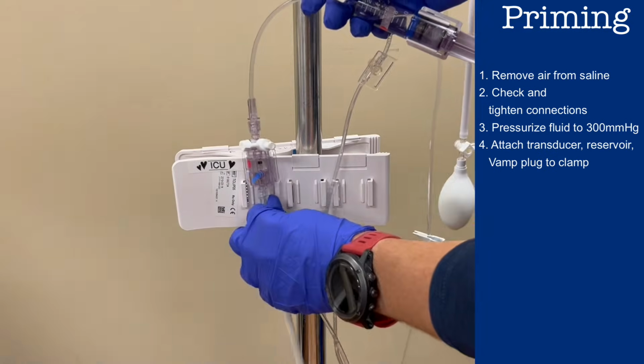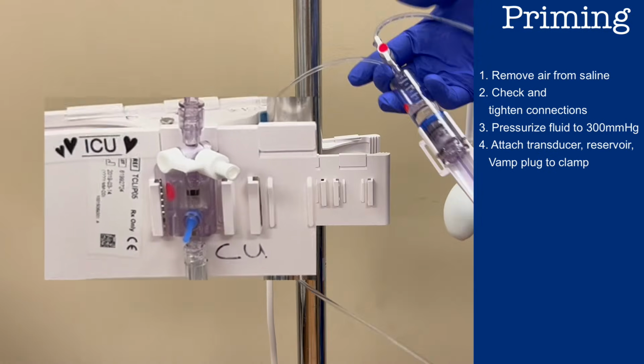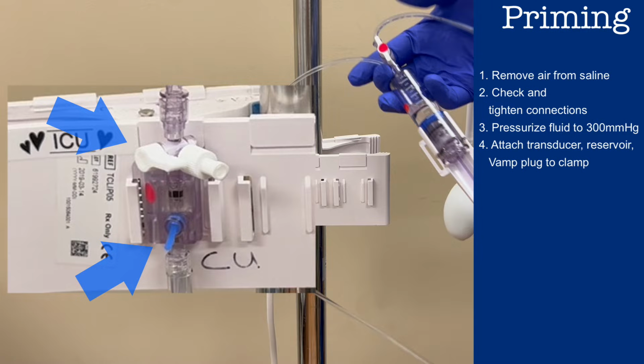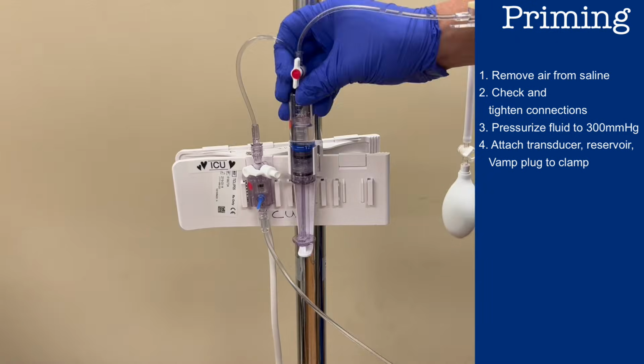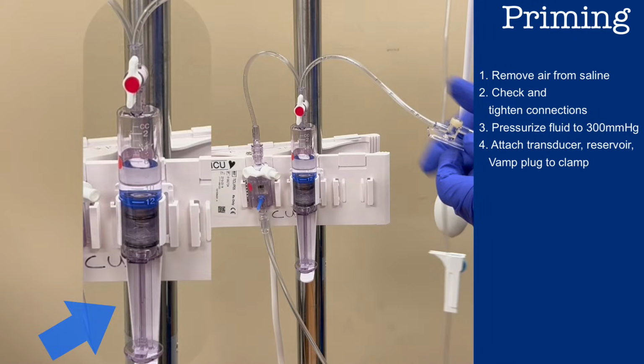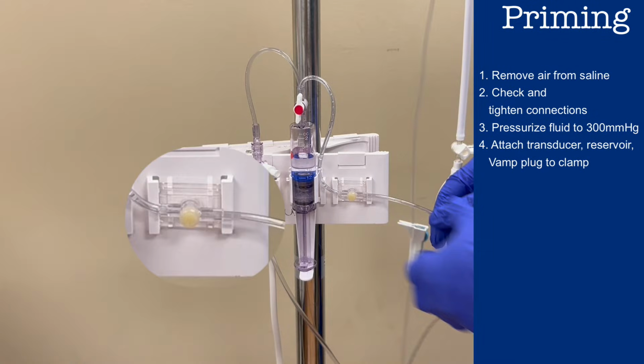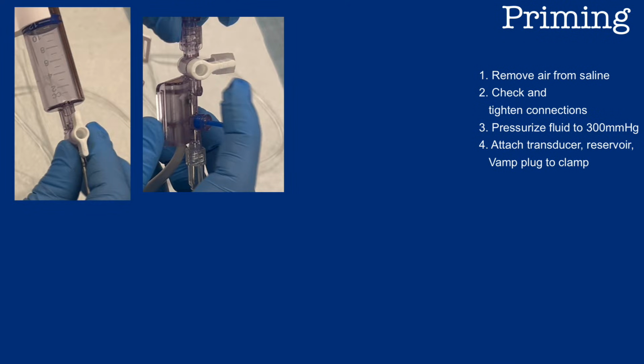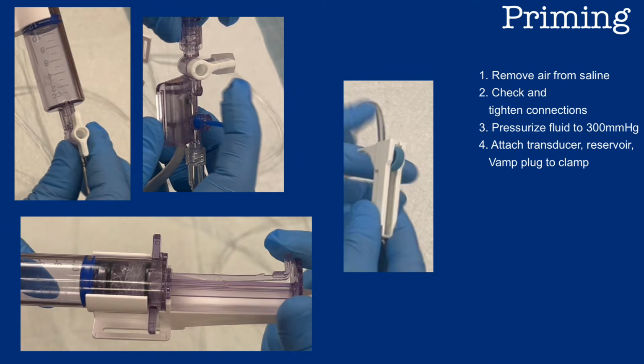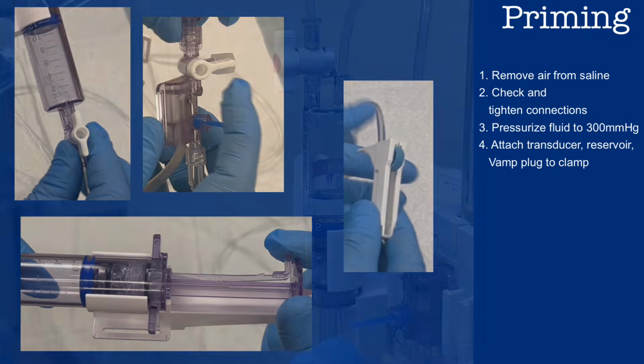Next, attach the tubing to the clamp. Slide the transducer into the bracket so that the stopcock is on top and the pigtail is on the bottom. Slide in the reservoir so that the plunger is on the bottom and the tubing attaches to the top. And slide in the vamp port closest to the reservoir, oriented horizontally. The stopcocks, reservoir, and roller clamp are all packaged in the required position to begin to prime the system, so there is no need to manipulate any of these at this point.